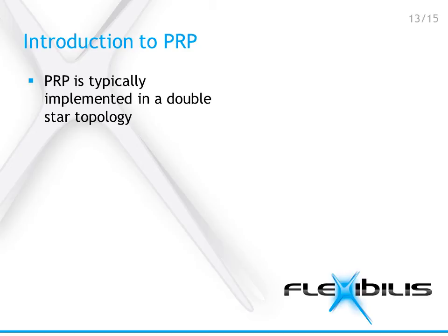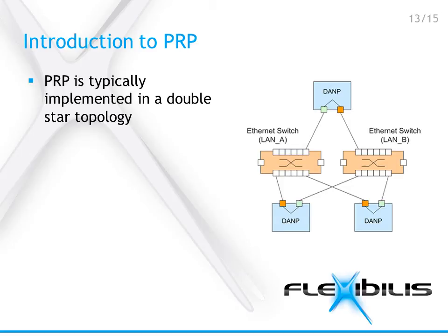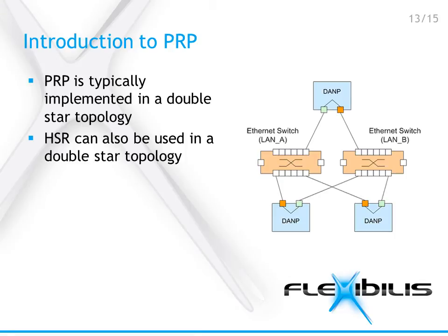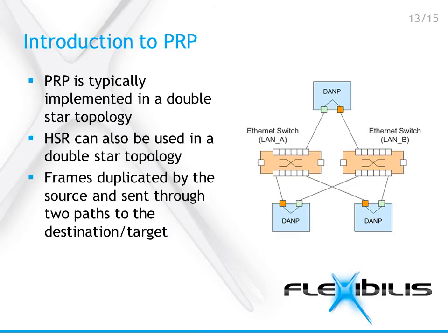PRP, on the other hand, is typically implemented in a double star topology, though HSR can also be used in this same topology. In double star, each node is connected to two separate parallel local area networks. As in HSR, the source node in PRP also sends two copies of each packet, one over each network. PRP requires that everything is doubled — the switches, the cables, and the data. HSR doesn't require as much cabling and doesn't need dedicated switches, so it's less expensive while still providing the same level of redundancy.